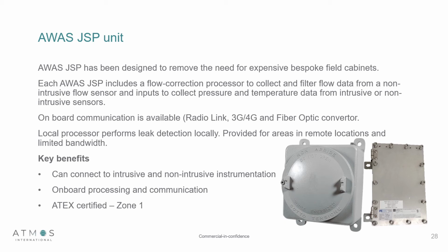Now, why would we use a JSP over an Eclipse? Well, the Eclipse unit can only work on up to a 30-inch diameter due to the length of its ATEX body. The ability to have a JSP means we can go on to much larger diameter pipelines, and also it can handle much more extreme conditions. For example, we can install this in very, very cold temperatures or very, very hot temperatures. It means that Atmos has assessed the challenges and it has combined different technologies to meet those ones.